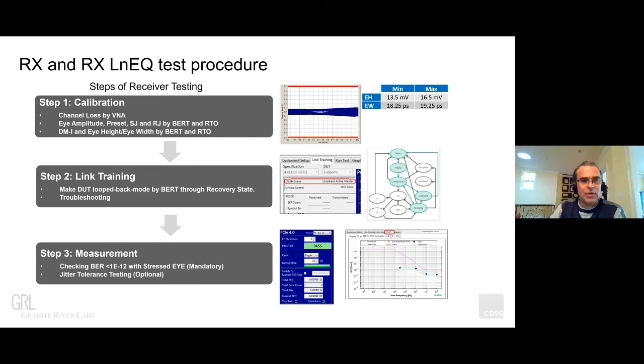Depending on the data rate, your test time will decrease. For Gen 3, it's about 125 seconds. For Gen 4, about 62 seconds. For Gen 5, it's about 32 to 35 seconds. When testing is done, you're allowed only one error in Gen 3, Gen 4, or Gen 5. That error isn't correctable, but one is allowed at a BER ratio of 1e-12.